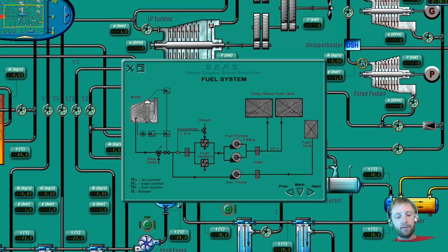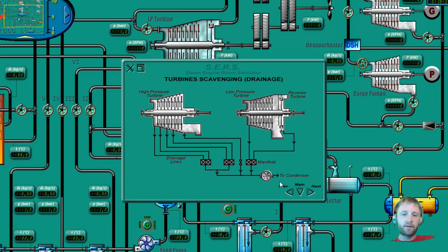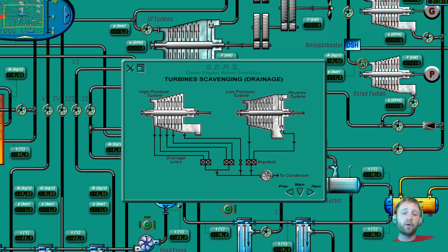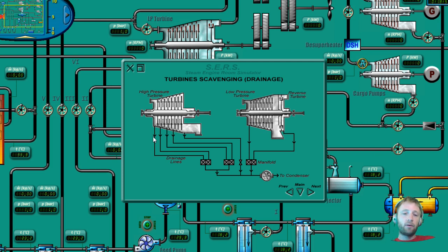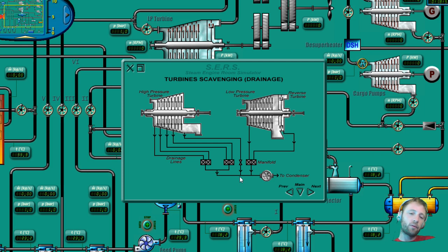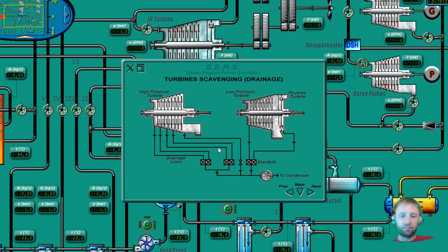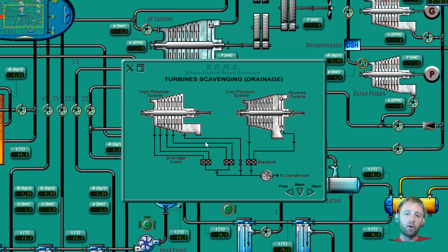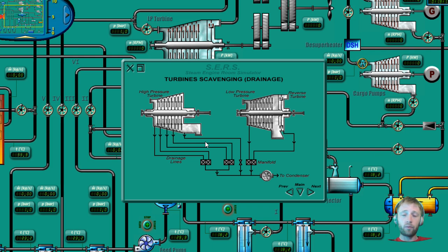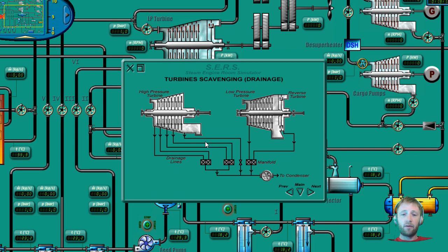Let's see the next sketch. We have turbines scavenging drainage. We have our high pressure turbine, low pressure turbine which is also a reverse turbine, and all the drainages here going to the manifolds and from there to condenser. So all this water will be back to the condenser and will be reused again. So we have a closed loop of our system. For sure there will be losses from the hot well tanks and from the evaporation from some open tanks, but we have a closed system.